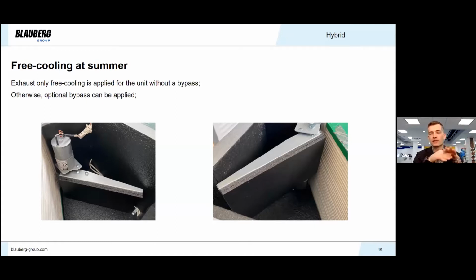Also, the decentralized modification is equipped with a bypass. Truly saying, there is no need for a bypass from the point of view of eco-design, because power consumption is low, it is below 30 watts per fan. It is installed in the hybrid max modification just to provide maximum comfort, considering small classrooms as one of the main applications. At the same time, we decided not to apply the bypass in the centralized modification of the units in order to simplify it as much as possible.